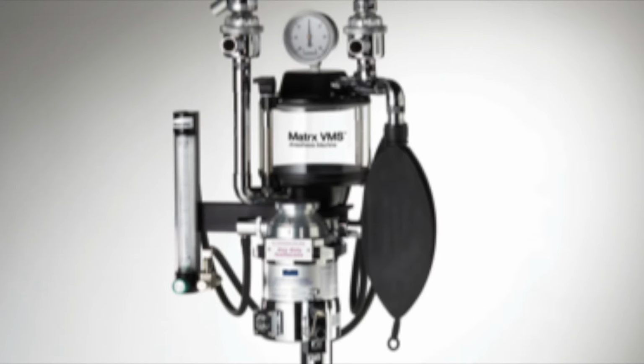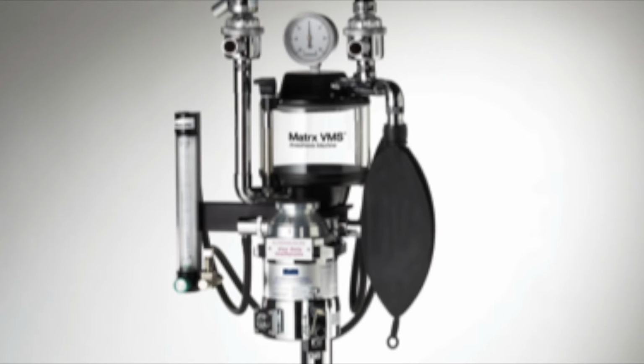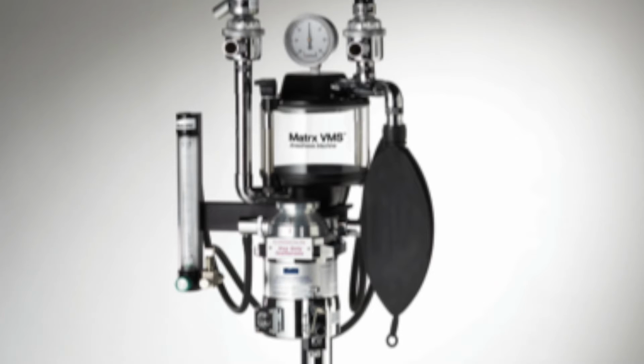Then, as we move past, we can see our vaporizer, which is isoflurane. Oxygen then enters through the inlet port to the vaporizer and will then be mixed with a set amount of anesthetic vapor and come out with a mixture of oxygen and isoflurane anesthetic at the outlet port. The outlet port then contains a tubing, which then connects to the fresh gas inlet, which contains oxygen and anesthetic gas.